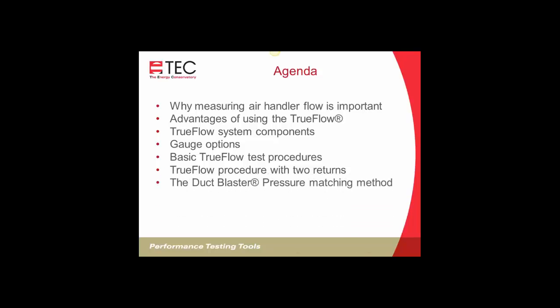And then we'll talk about using the Duct Blaster. The Duct Blaster can be used to measure air handler flow, and we'll talk about using that method. If you already have a Duct Blaster fan, you can use it to measure the total air handler flow, not just the duct leakage. And then we'll talk about troubleshooting airflow problems. So if you measure the airflow and it's an issue and you're not sure what the next step is, we'll talk about troubleshooting some of those flow problems that you might have with your air handler system.